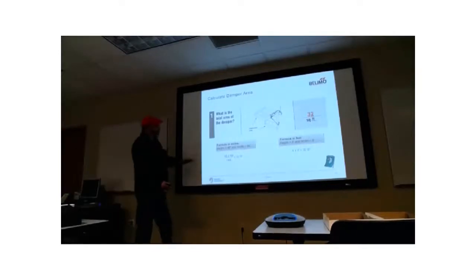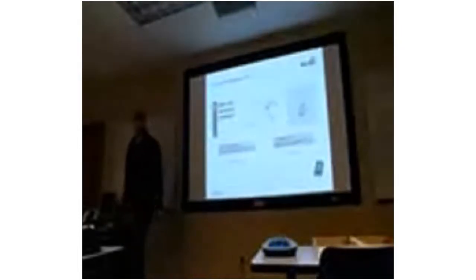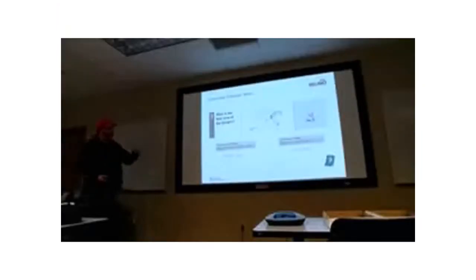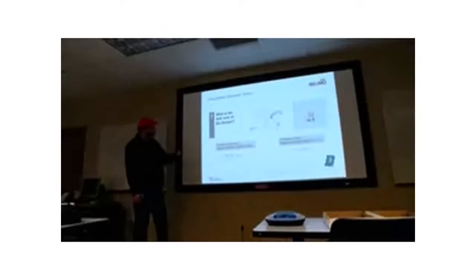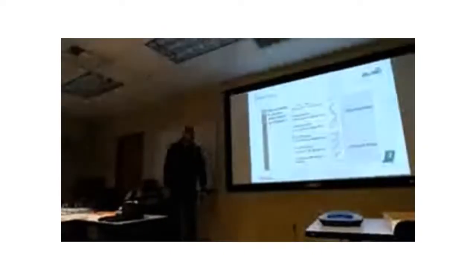That's the size of our damper and face area. So what I'm talking about is just what we call the face area. What's another area applied to dampers? It's called free area, right? So what's free area, do you think? That's the area between the damper blades, right, that the air actually goes through. So engineers will talk about face area. They'll also talk about free area. So a certain damper type might have different free area, depending on the way the damper is constructed. But we want face area. So that's number one. Number two is, what is the type of damper?